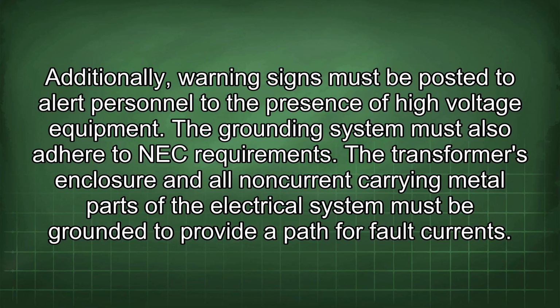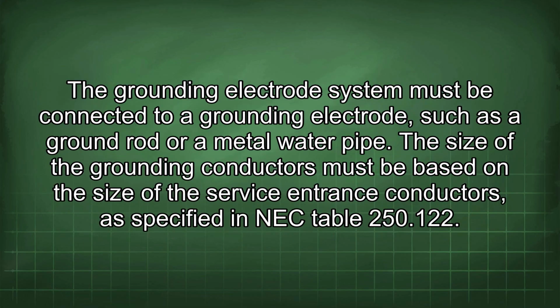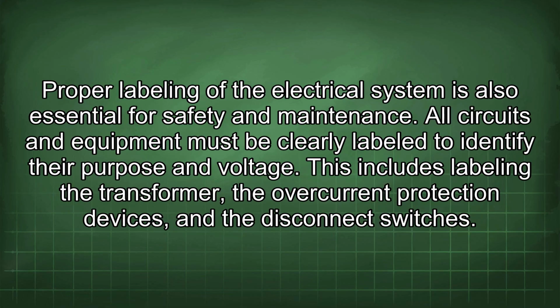The grounding system must also adhere to NEC requirements. The transformer's enclosure and all non-current carrying metal parts of the electrical system must be grounded to provide a path for fault currents. The grounding electrode system must be connected to a grounding electrode, such as a ground rod or a metal water pipe. The size of the grounding conductors must be based on the size of the service entrance conductors, as specified in NEC Table 250.122. Proper labeling of the electrical system is also essential for safety and maintenance.